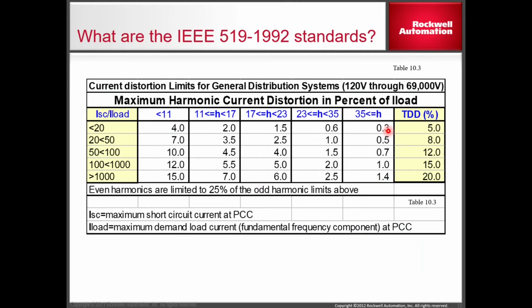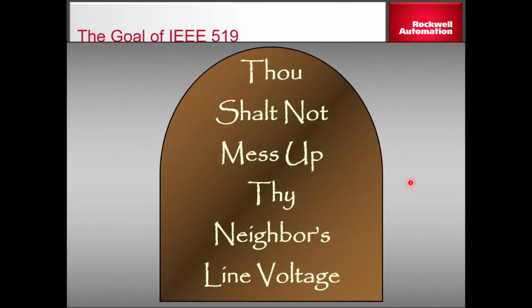And the current distortion limits are here as follows. Depending on your short circuit load versus your current load, those ratios will change how much allowable distortion you can have. So everybody knows the 11th commandment, right? Thou shalt not mess up thy neighbor's line voltage.